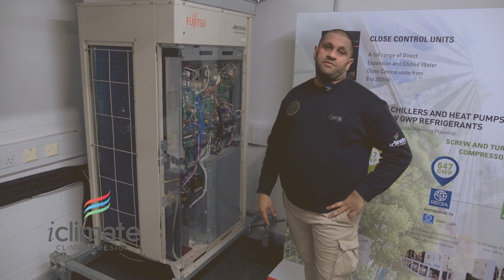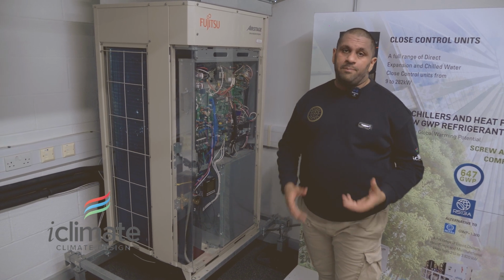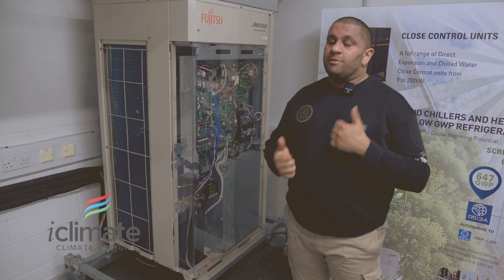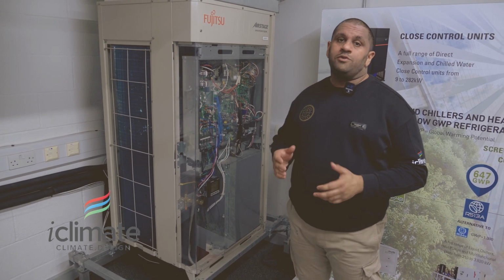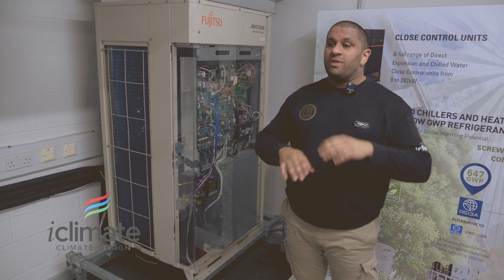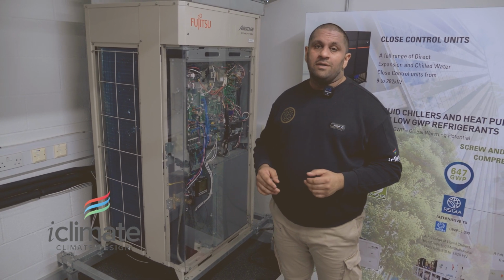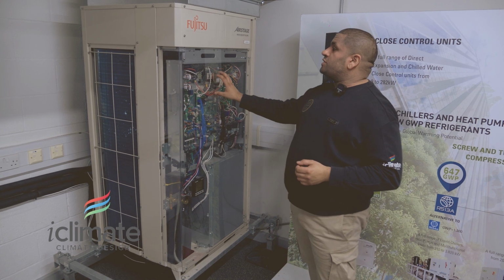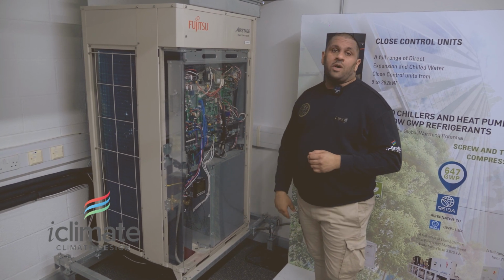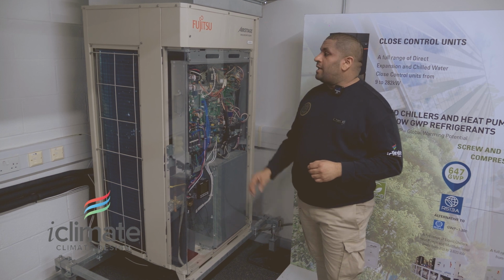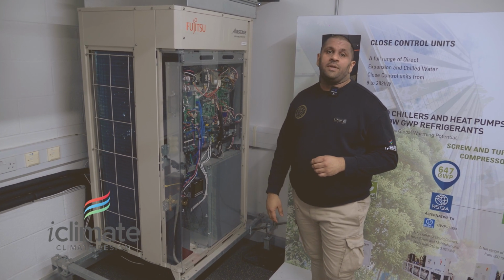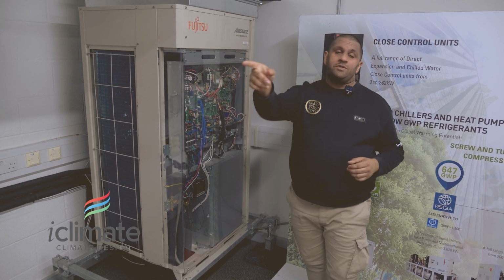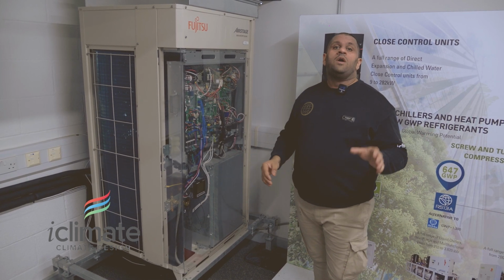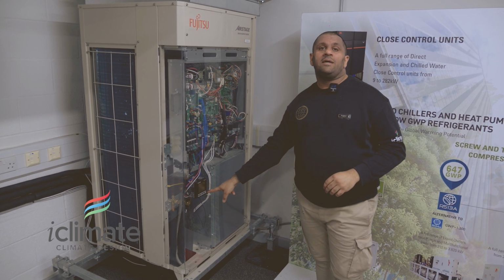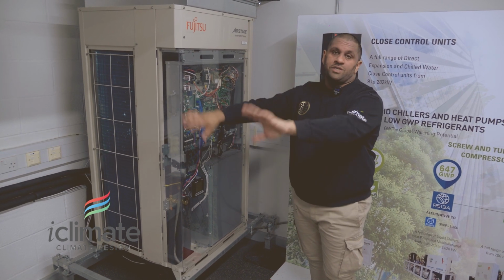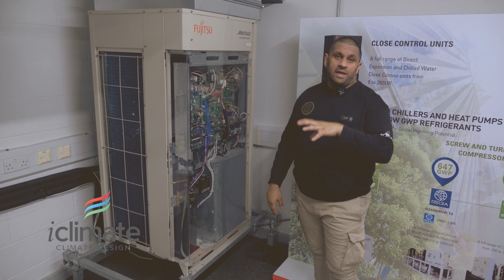These central heat recovery VRFs come in the heat recovery variant and they also come in the heat pump variant. So if you don't wish to have simultaneous heating and cooling across a common system and you just want a typical air conditioning orientation where the system is on an all heat or an all cool setting across the indoor units, then you can also have a large capacity VRF that can serve up to 12 to 15 dedicated indoor units. The only difference between the heat recovery and the heat pump is if you wish to have the heat recovery, you'll have the distributor box in between that will distribute to the fan coil units, whereas the heat pump will have two pipes coming into here, and this will do all the distribution across the refrigeration network to the indoor units for that given mode.